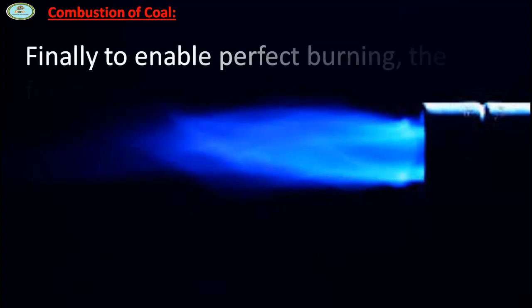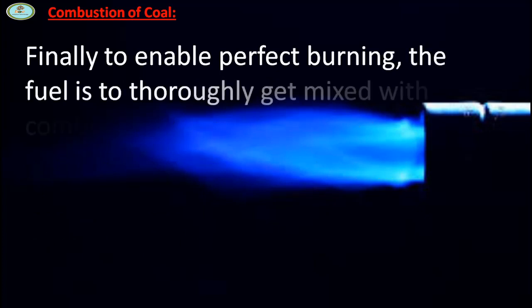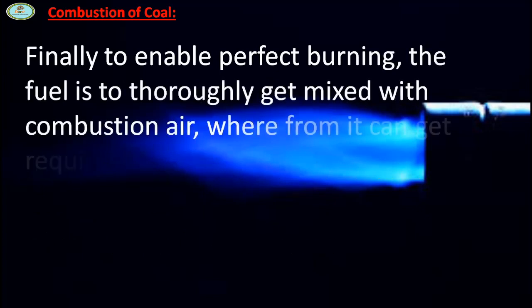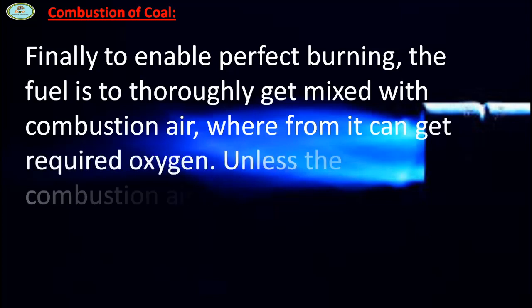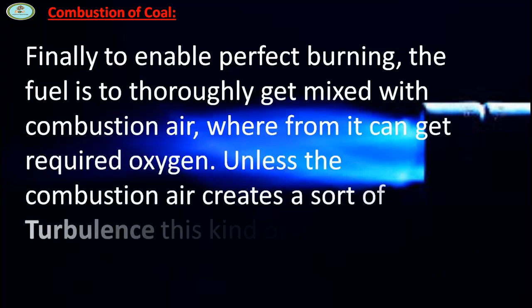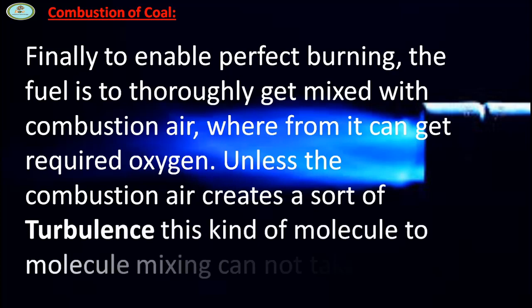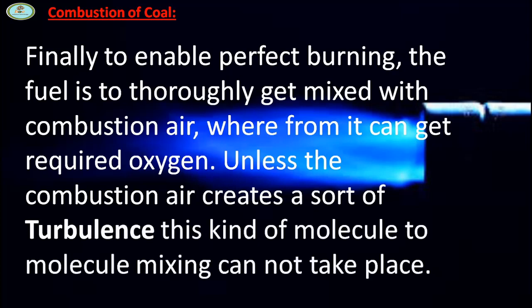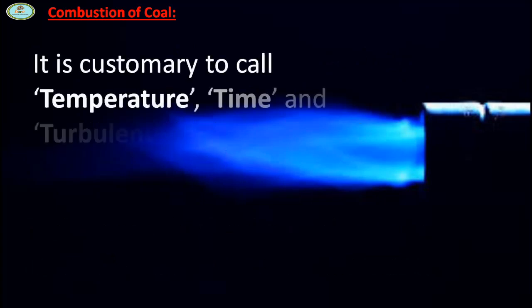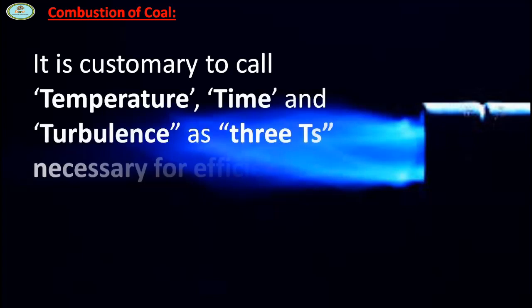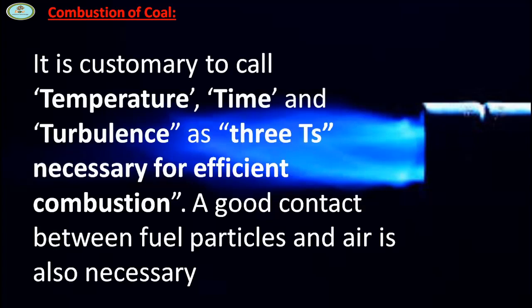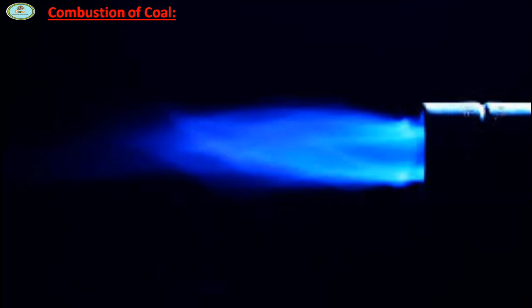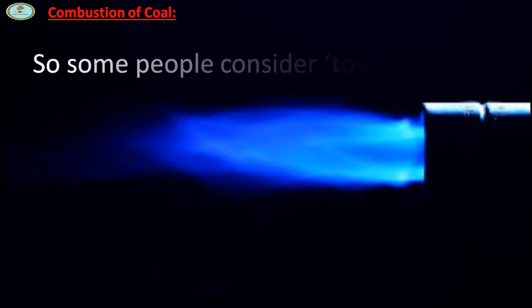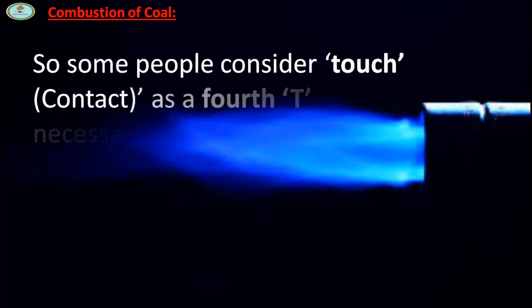Finally, to enable perfect burning, the fuel has to be thoroughly mixed with combustion air, from where it can get the required oxygen. Unless the combustion air creates a sort of turbulence, this kind of molecule to molecule mixing cannot take place. It is customary to call temperature, time and turbulence the three T's necessary for efficient combustion. A good contact between fuel particles and air is also necessary, so some people consider touch as a fourth T necessary for efficient combustion.